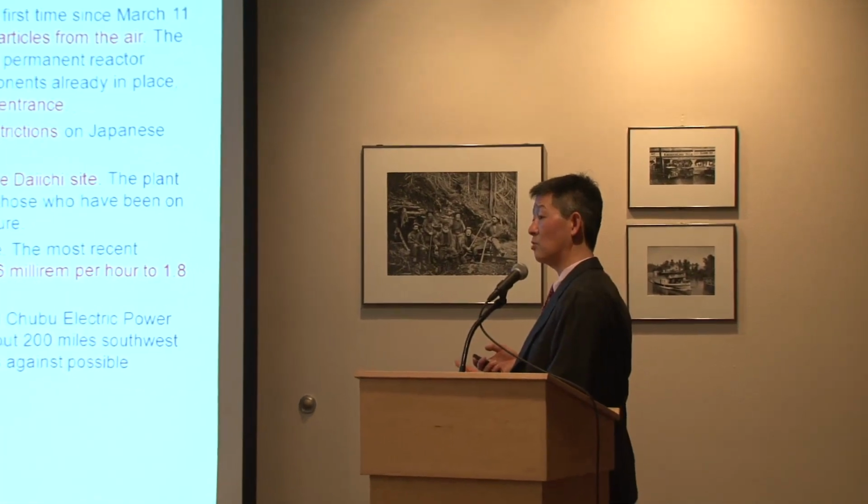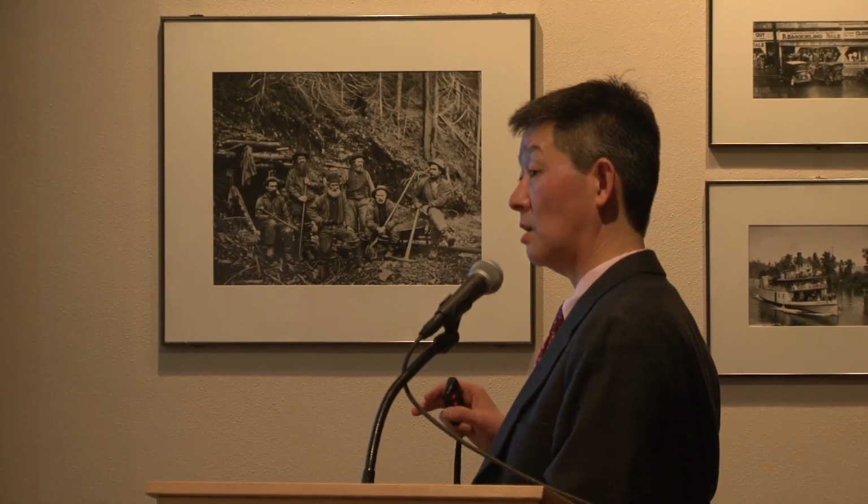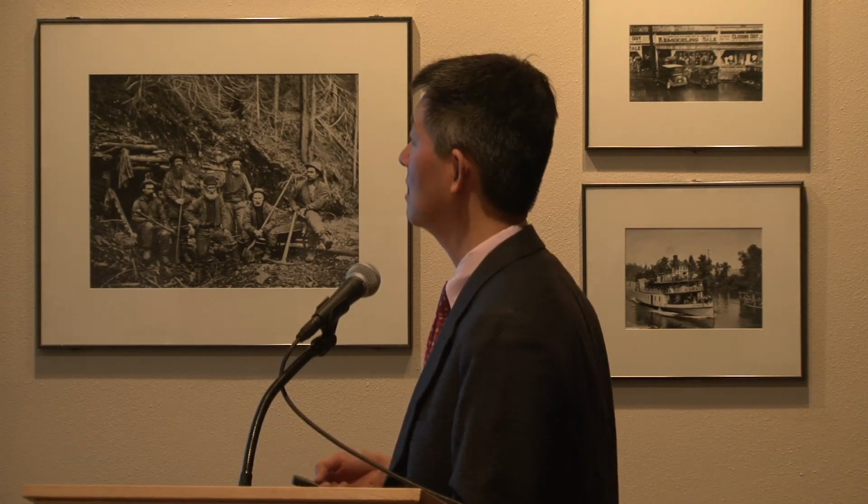There was an early iRobot video clip, and they went into Unit 3 and 4 at the ground floor, and it was such a sauna there, 99% humidity and high temperature. They had a radiation detector, and you could not even see the LED display because there was so much humidity. It was like trying to read a silvery LED display inside a sauna. You couldn't see it. Okay, so they said, we need to have a dehumidifier, take the humidity out of the air. They've just installed a number of dehumidifiers with a particulate filter to take some of the airborne radioactive moisture out of the air.